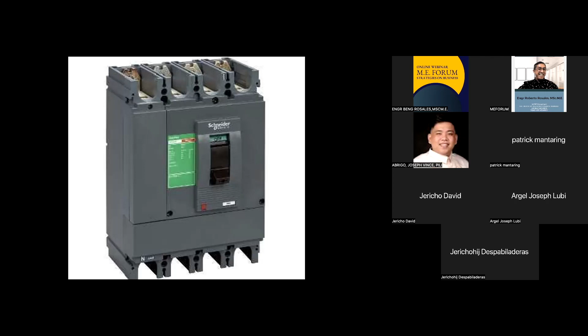miniature. It's a case-to-case basis. But most, if I'm correct, based on what I saw on the internet, I think this is a 500 ampere trip Schneider breaker. Now, the next slide shows you the ampacity table. The wire we use is THHN. If the picture is too blurry, I apologize for that. But what we use is copper at 90 degrees.